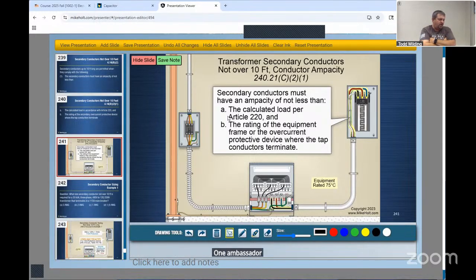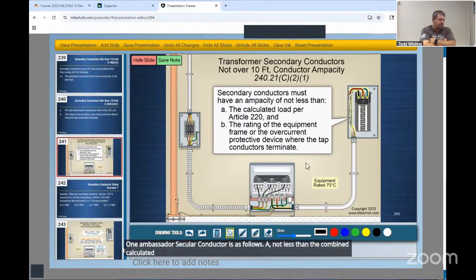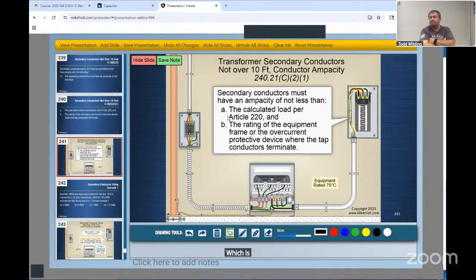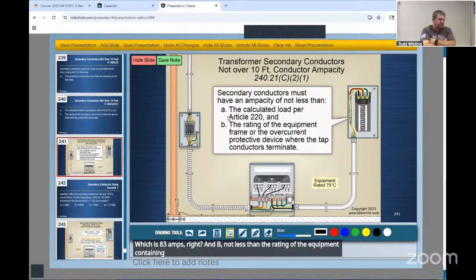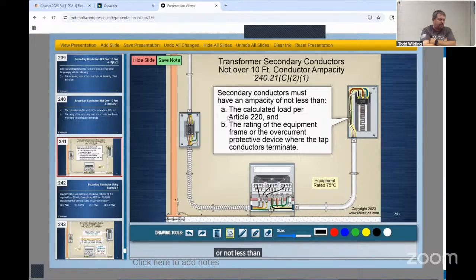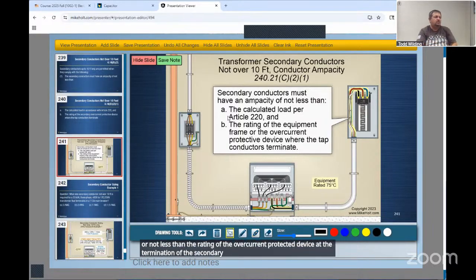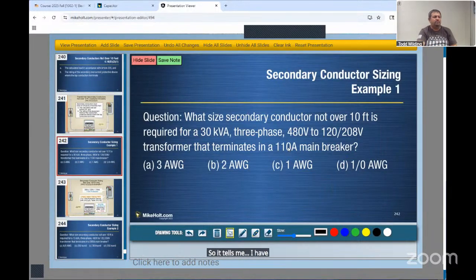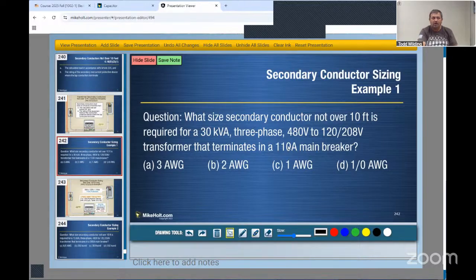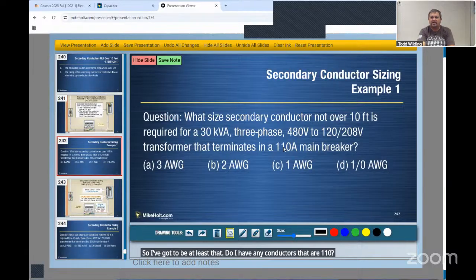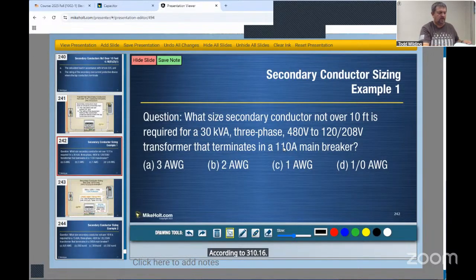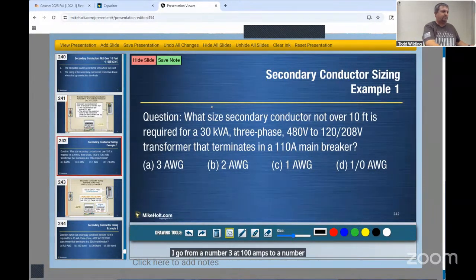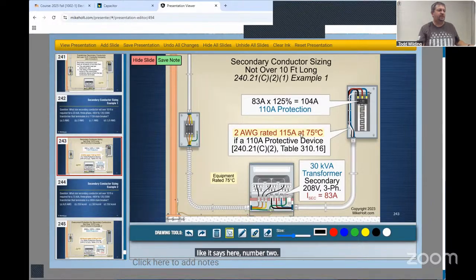1, ampacity of secondary conductor is as follows. A, not less than the combined calculated load on the circuit supplied by the secondary conductors, which is 83 amps, right? And B, not less than the rating of the equipment containing an overcurrent device supplied by the secondary conductors, or not less than the rating of the overcurrent protective device at the termination of the secondary conductors. So it tells me I have a 110 amp main breaker. So I've got to be at least that. Do I have any conductors that are 110? According to 310.16, I do not, right? I go from a number 3 at 100 amps to a number 2 at 115 amps. Like it says here, number 2, 115 amps.